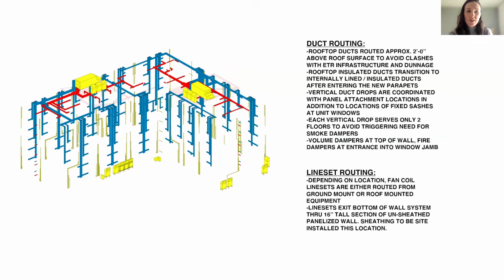The vertical duct drops, you can kind of see in the diagram here, are carefully coordinated with panel attachment locations, and they want to align and get you to the fixed sash of every window, which presented its own set of challenges. And really important here is that each set of duct drops only serves 2 floors at a time. Otherwise, we would be triggering the need to install smoke dampers. Our fire alarm system cannot handle those. It doesn't have the capacity for them. And you'd also have some access requirements that we wouldn't be able to accommodate with this solution. So it became very, very important to fine tune the design around that.